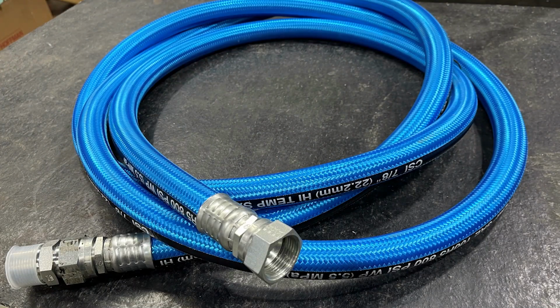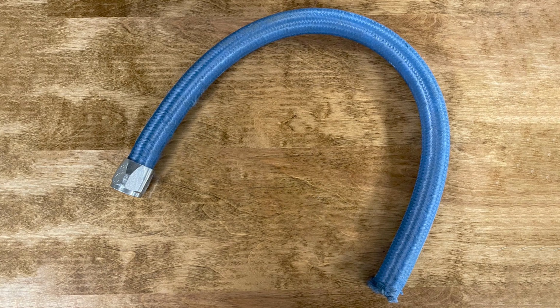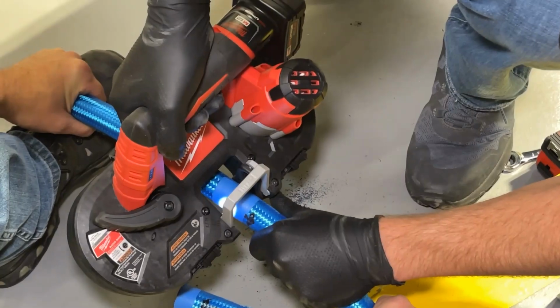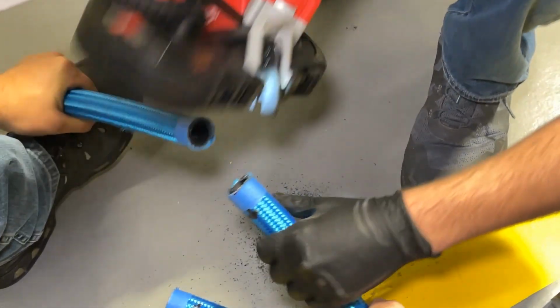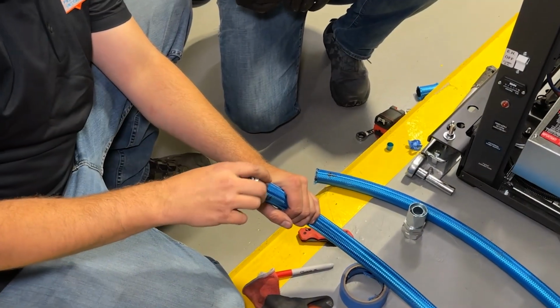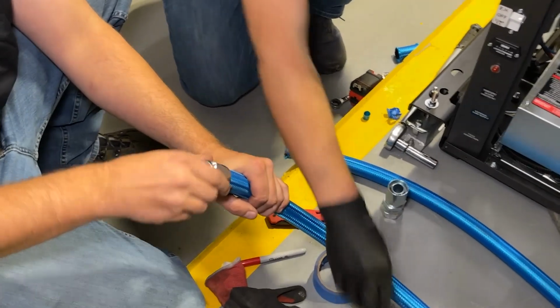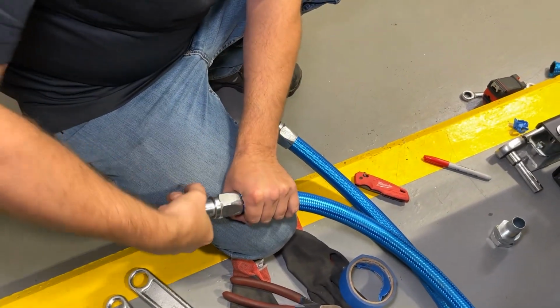Once fittings are secured, prep the hoses for installation. Hotstart recommends the use of cut-to-length, steel-reinforced braided type hoses with fittings already attached. Alternatively, hose can be sourced with the fitting pre-installed on one end and bare on the other. This will allow for the hose to be cut to a specific length during installation. Once you have measured and cut the hose to the desired length, install the second fitting to the hose.